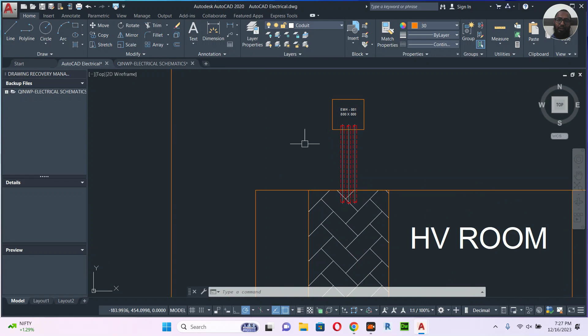And then the main thing I didn't tell in the previous video: normally I'm working in Qatar. Normally in Qatar, they give a 3 core 240 cable. So you may have big cables from the MV room, like 4 core or 3 core 240, or 3 core or 4 core 300, and you may have a bunch of 4 core 300 cables. But the HV room only gets one cable because we have only one transformer. Even if you have 2-3 transformers, only one cable will come, and it will be distributed from here. The one cable will be 3 core 240.